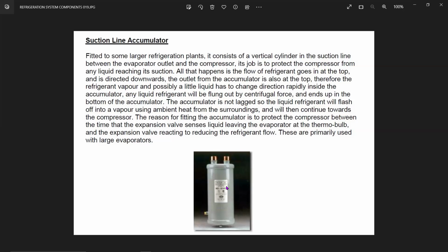Flashing off immediately. Okay, that is the reason: it is preventing the liquid from reaching the compressor. Accumulator क्या होगा? Accumulator is preventing the liquid from reaching the suction line to the compressor. ठीक है? So again, this has got its limitations. अगर ये बहुत ज्यादा आपका liquid आ जाएगा तो it will not be able to handle because evaporation rate, तो area तो छोटा ही है ना इसका in comparison with the entire thing. It is having a very small area in comparison with the entire evaporator and the lines.